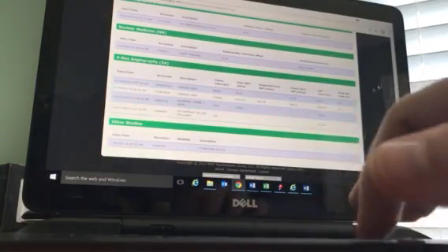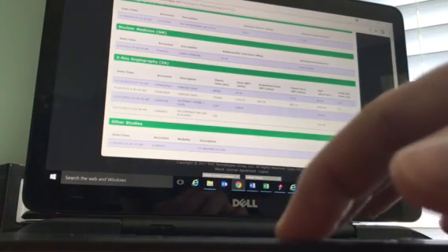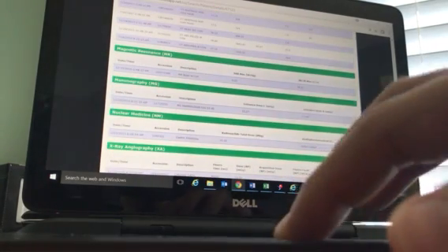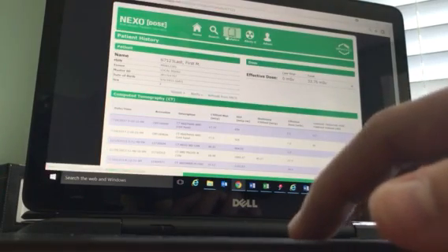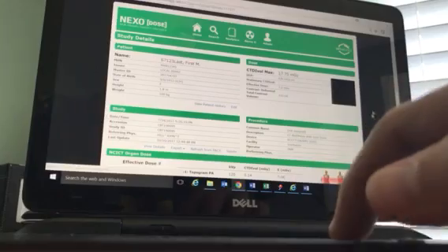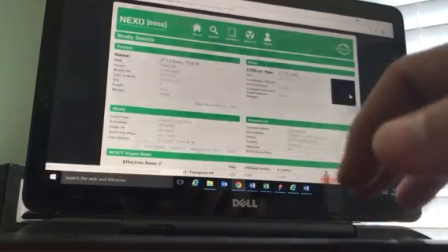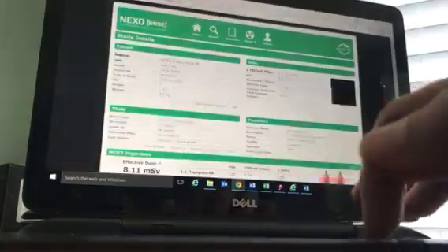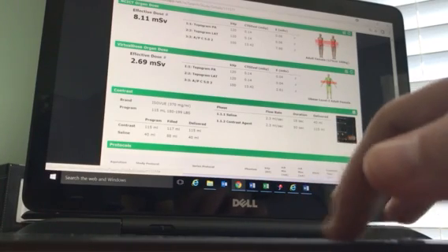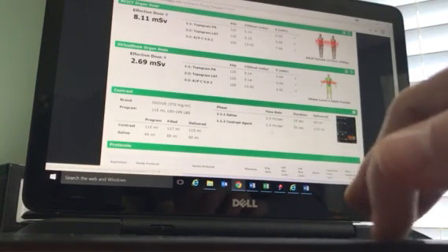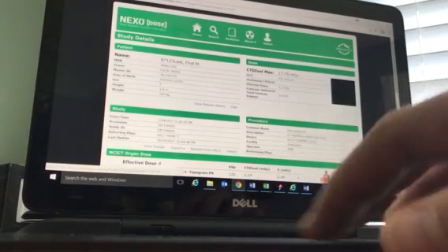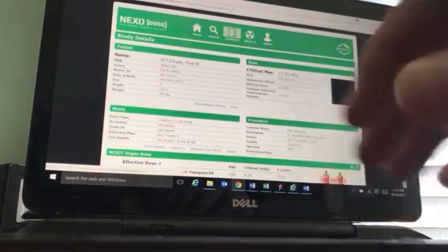Angiography, we do peak skin dose. MRI, we're getting the SAR reading from the scanner as well. And if we go into one of the patients, we can get our structured dose report, which is here. And we can get both of our organ dose readings as well as contrast if you're using the Bracco Empower injectors and Nexo. Now I want to show you how to run an analytic.